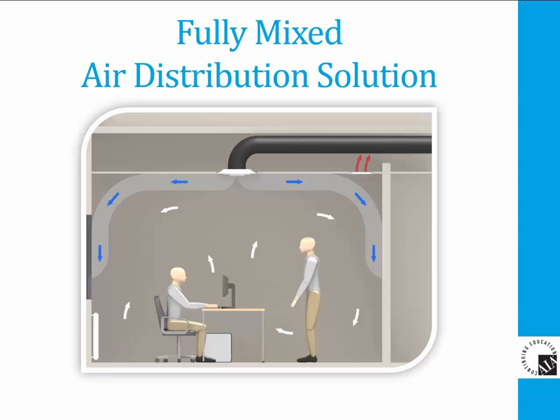Fully mixed systems rely on induction of room air into the supply airstream to comfort-condition the occupied space without drafts, and to compensate for external loads such as windows, computer equipment, and people. Supply air introduced into the space through ceiling or sidewall outlets may use ceiling or wall surfaces to mix and thermally condition the space to maintain optimum space temperatures for occupant comfort.